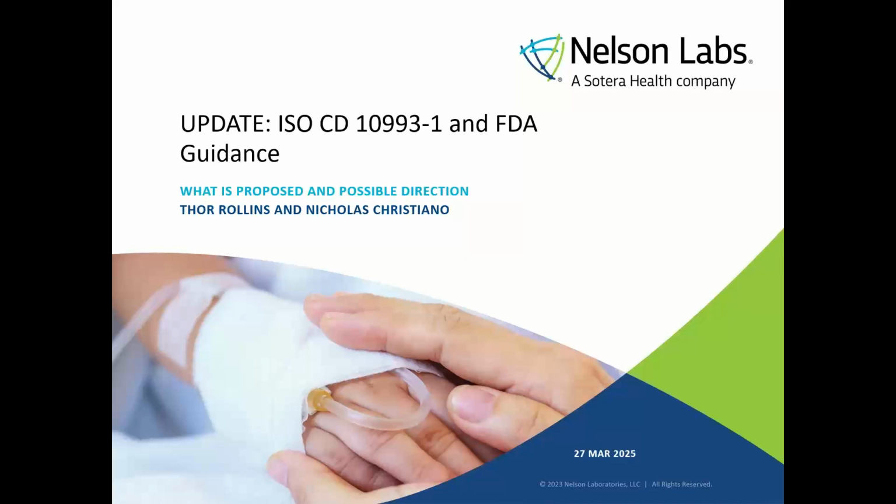If a medical device has manual cleaning or automatic cleaning claimed in the IFU, is it enough to prepare devices for biocomp after lifetime with manual and automatic cleaning separately, or do we have to consider sequential manual and automatic cleaning for preparation of articles for biocomp? Yeah, this is a great question.